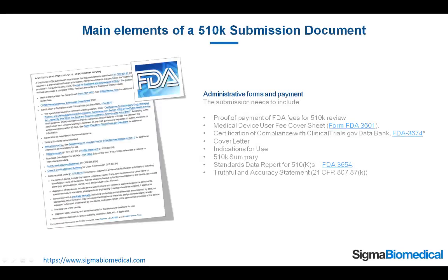Administrative Forms and Payment. The submission needs to include: proof of payment of FDA fees for 510k review; Medical Device User Fee Cover Sheet; Certification of Compliance with ClinicalTrials.gov Data Bank (FDA 3674); Cover Letter; Indications for Use; 510k Summary; Standards Data Report for 510ks; and Truthful and Accuracy Statement.